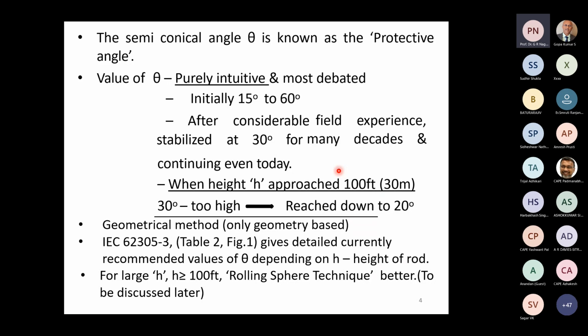When height approached 100 feet, it was found in practice that this did not work efficiently. 30 degrees was too high. The protection area was not equivalent to the circular area, which corresponded to 30 degrees semi-conical. Therefore, the protective angle theta of figure 2 was reduced to 20 degrees. So this depends purely on the geometry. Therefore, it's known as the geometrical method. The table 2, figure 1, which I showed just now, gives detailed currently recommended values of theta depending on the height of the rod. For large height, h greater than 100 feet, it is recommended that the rolling sphere technique is to be used. We'll be discussing it presently.